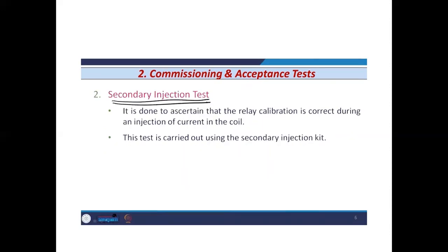The second one is the secondary injection test. It is done to ascertain that the relay calibration is correct, by injecting current in the coil. This test is carried out using the secondary injection kit. A kit is used to verify the calibration, because for any instrument calibration is very crucial. If it is not calibrated correctly, how can we verify whether it is up to the desired standard or not? So for that purpose a secondary injection kit is used to verify the calibration of the relay, and whether it is correct or not.